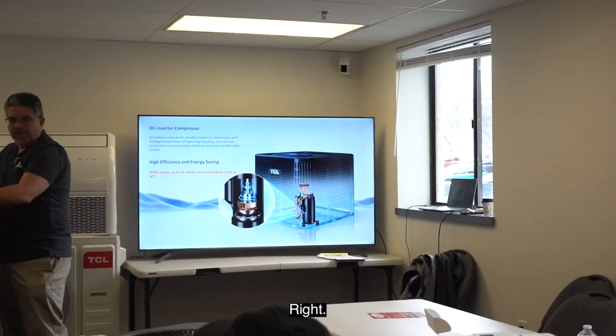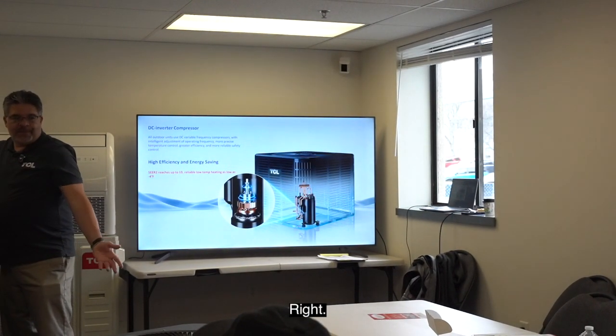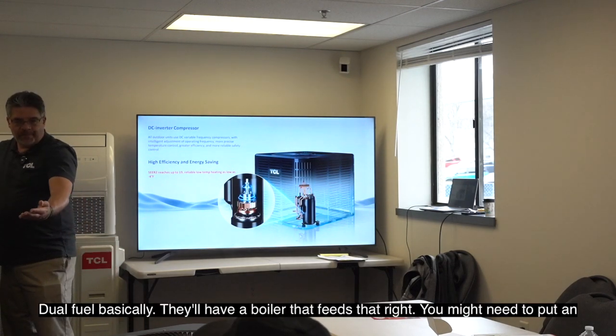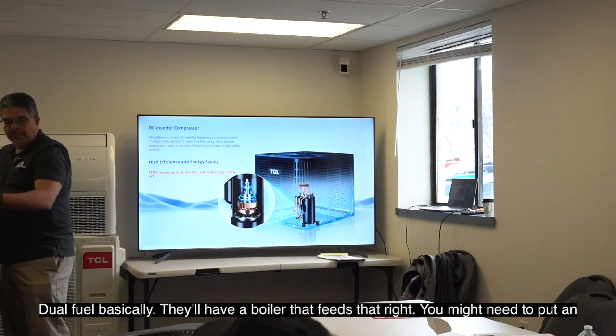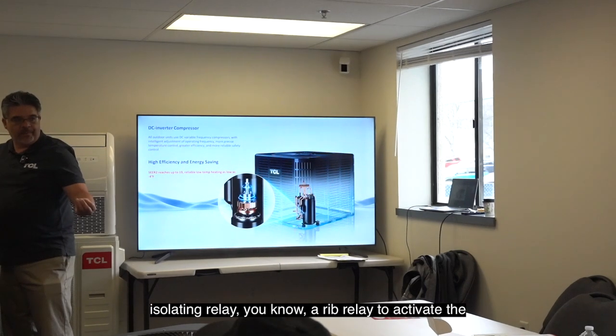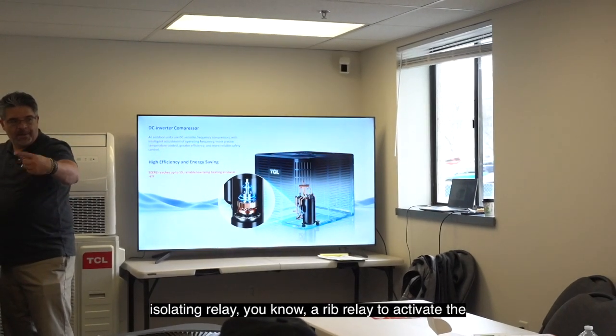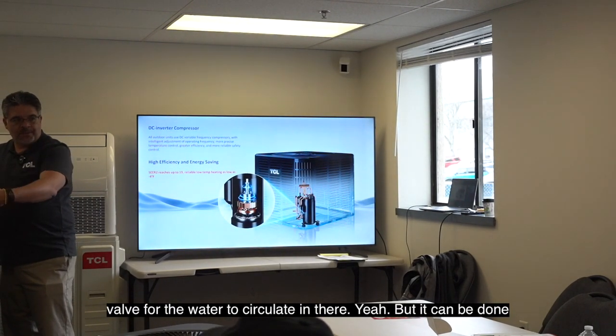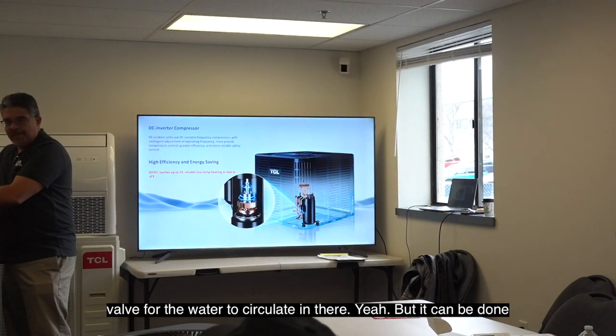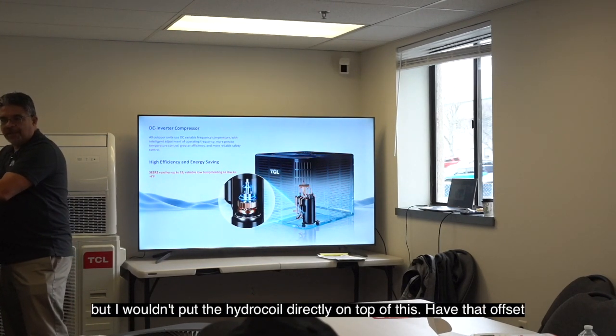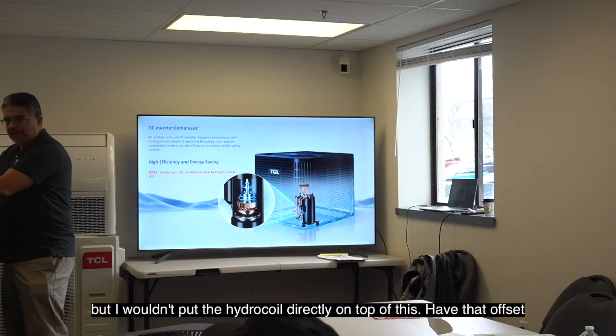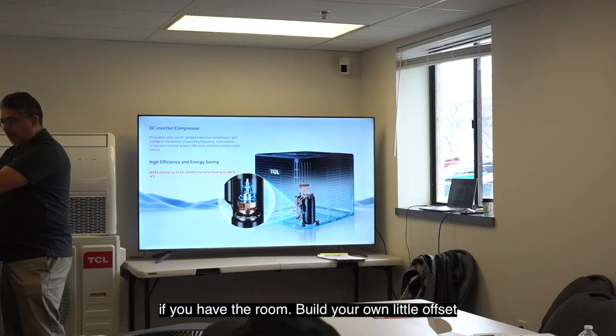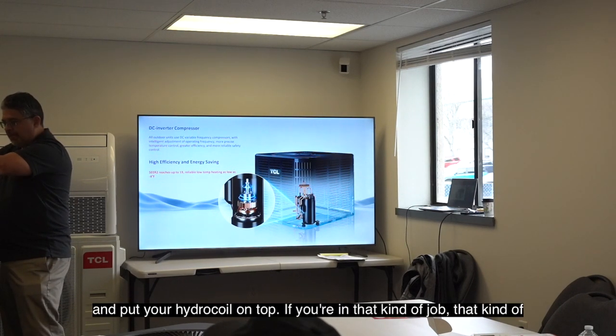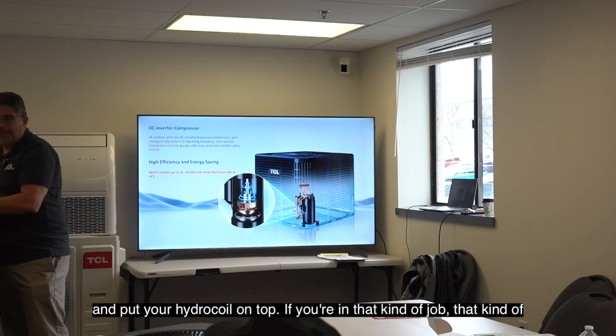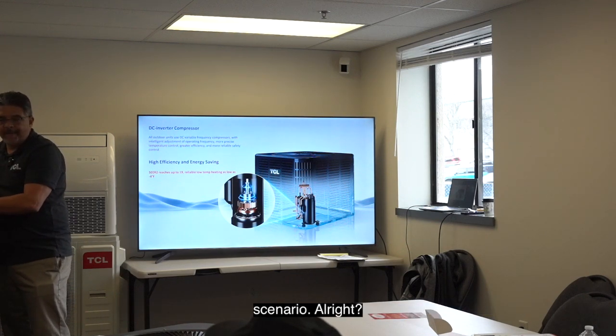All right. Backup heat. Right. Dual fuel, basically. They'll have a boiler that feeds that. Right. You might need to put an isolating relay, a RIB relay, to activate the valve for the water to circulate in there. Yeah. But it can be done, but I wouldn't put the hydro coil directly on top of this. Have that offset. If you have the room, build your own little offset and put your hydro coil on top, if you're in that kind of job, that kind of scenario. All right.